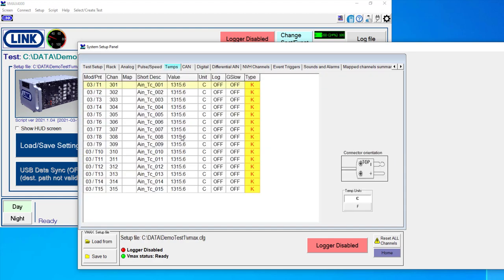Thermocouples, I've got a thermocouple input module, which can accept K, J or T type thermocouples. And you can change this on a channel by channel basis, up to 15 of those per module.